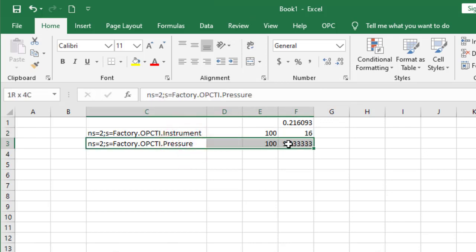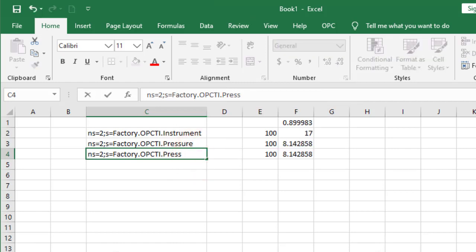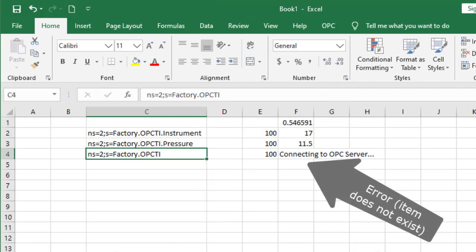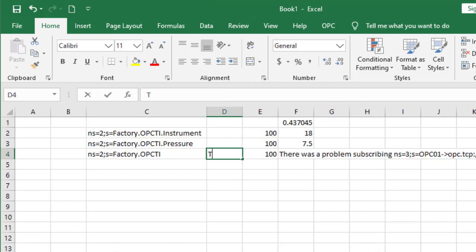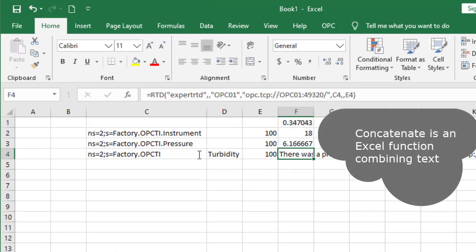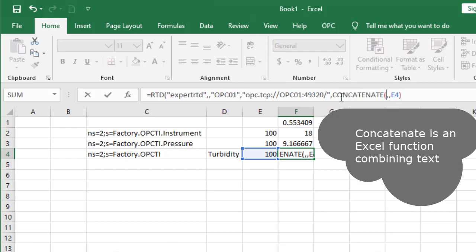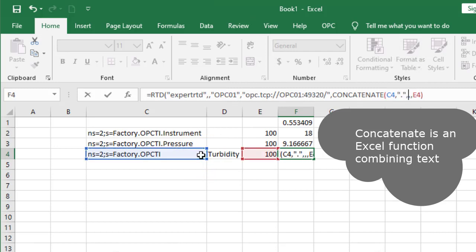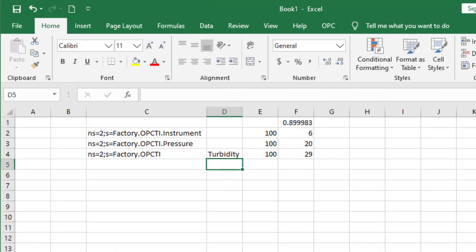Let's get deeper. First, we remove the item name. And notice, the last period is gone too. Of course, this item does not exist, so Excel's OPC RTD shows an error. We write the item name in a separate column. And now, tell Excel to combine separate cells using concatenate. Excel is going to concatenate, or combine, C4 with the period we removed, and we add the item name in D4. Excel now shows our turbidity item.